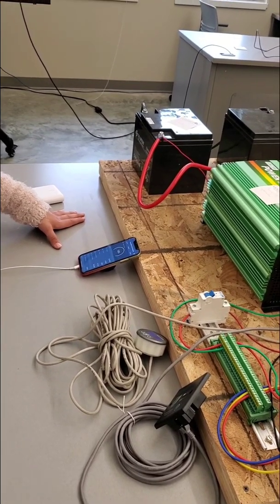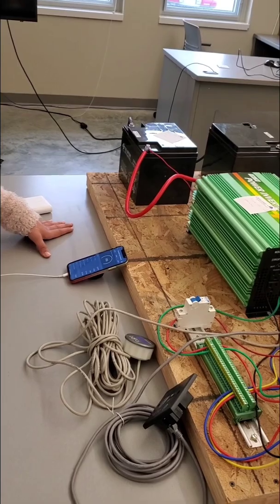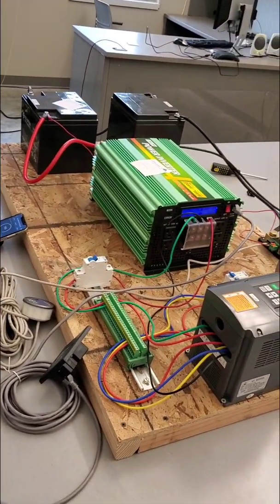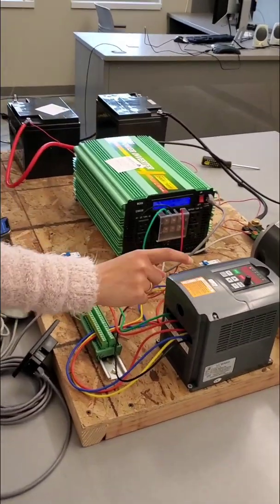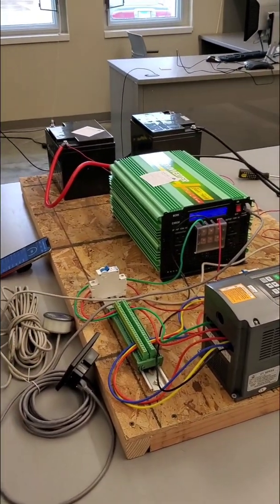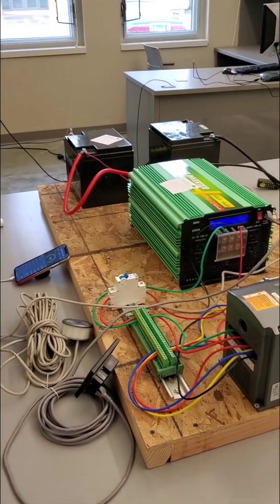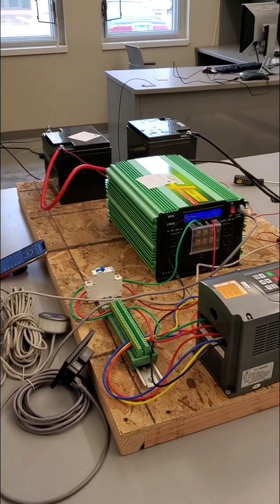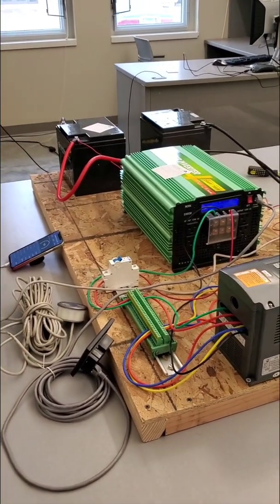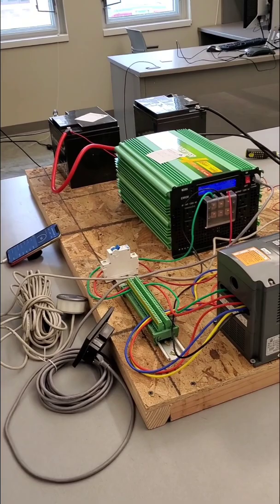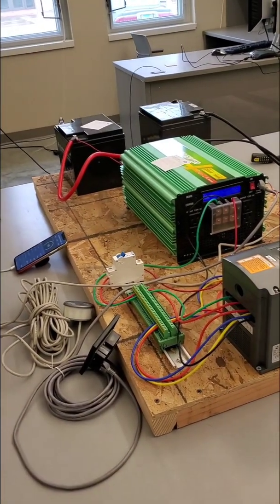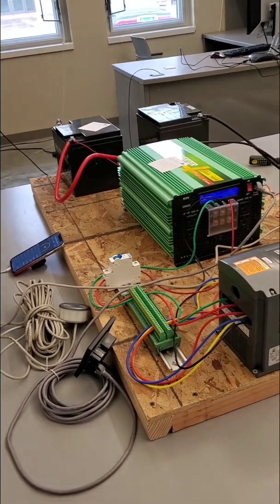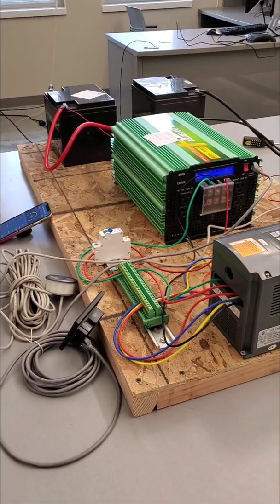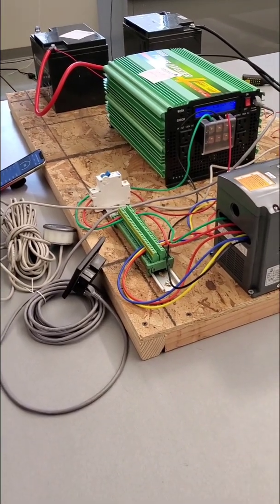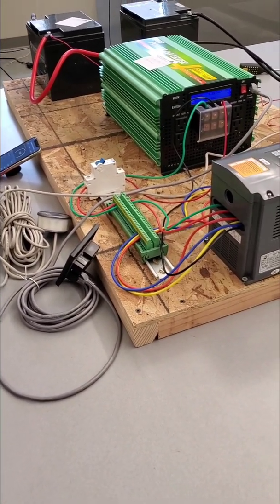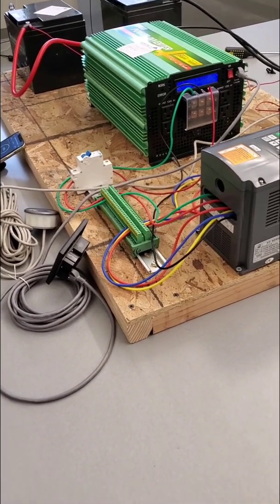Once you change voltage, you have to change frequency so that the flux will be the same. That's the basics of scalar control: both voltage and frequency at the same time, in order to maintain magnetic flux. Let's say the voltage is 110 and the frequency is 50 hertz. 110 divided by 50, that ratio is the constant, the magnetic flux, and we want to maintain that ratio throughout the operation. We have several methods of controlling, but this is only one aspect, the V/F control method.